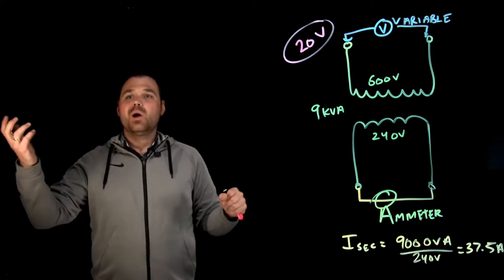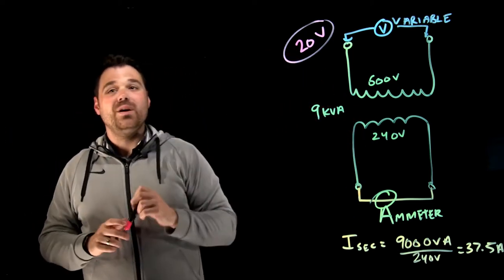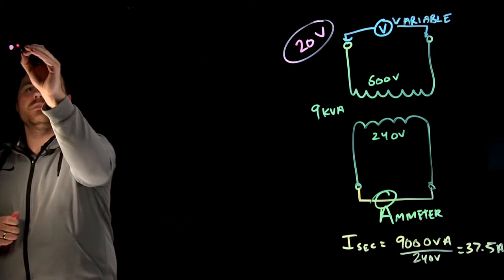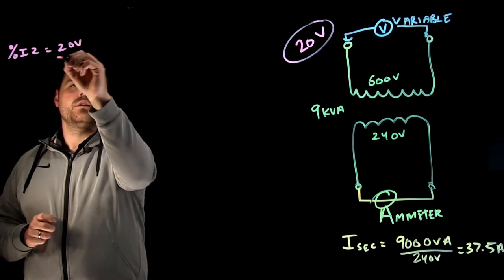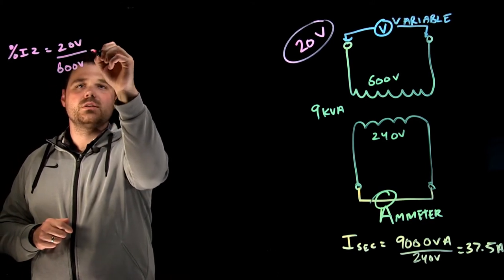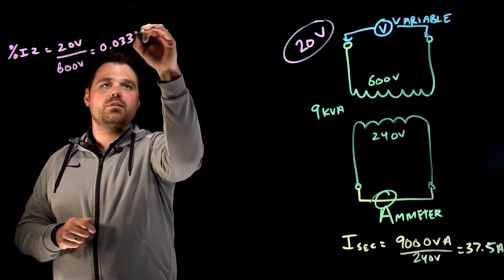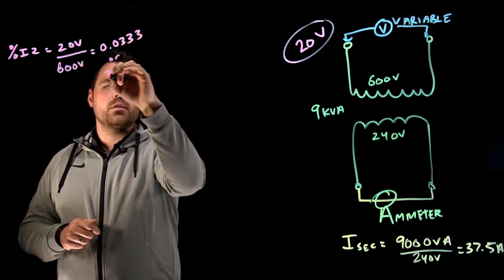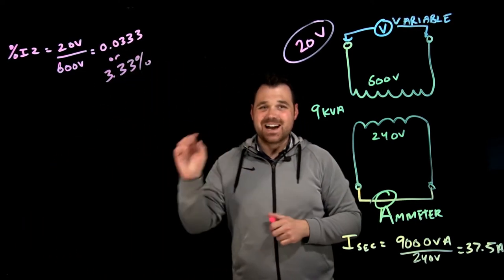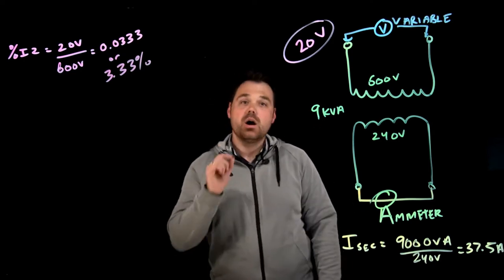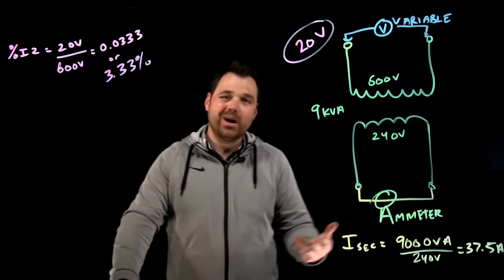So what do we do with that? Well, my percent IZ is 20 volts. So percent IZ will equal 20 volts divided by my rated voltage, 600 volts. So that equals 0.0333 or 3.33 percent. That is the percent IZ or percent impedance of my transformer. Now, like I said, it could be on the nameplate, but it isn't always.